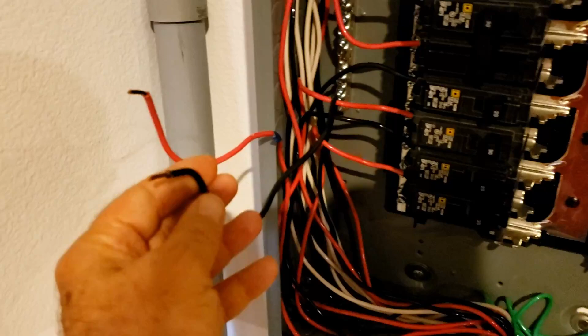Now I've got a couple problems here. One, this line is for the air conditioner, and this is hot - I haven't turned the breaker off yet, but these aren't connected to anything. This is just going through the wire to the ground, so it hasn't been connected to the box yet. These are for the air conditioner the guy put in. He has 10 gauge wire running down through here, and that's the spool. Since we haven't cut it off yet, we don't know how much room or wire we'll need to feed it through the wall to the condenser on the air conditioner.